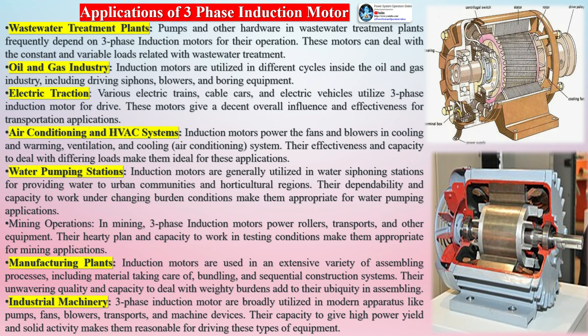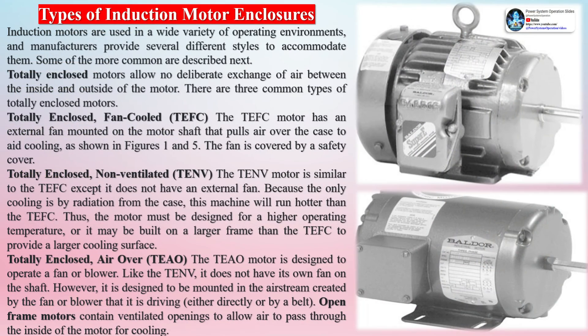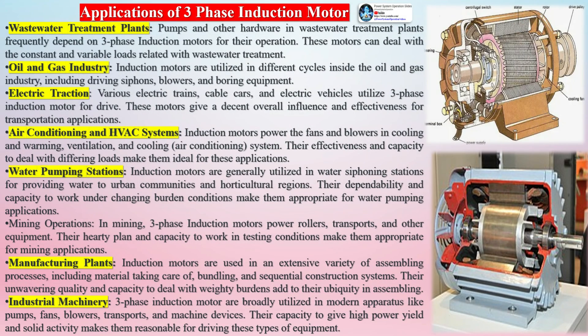Induction motors are used in a wide variety of operating environments, and manufacturers provide several different enclosure styles to accommodate them. Totally enclosed motors allow no deliberate exchange of air between the inside and outside of the motor. There are three common types: the Totally Enclosed Fan-Cooled (TEFC) motor has an external fan mounted on the motor shaft that pulls air over the case to aid cooling; the Totally Enclosed Non-Ventilated (TENV) motor is similar but does not have an external fan, so it runs hotter and may require a larger frame to provide a larger cooling surface.